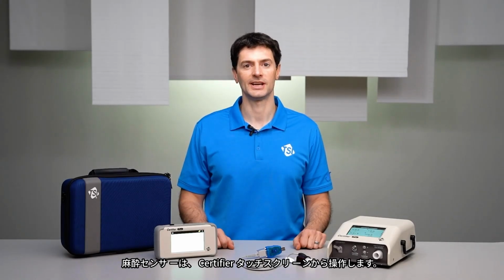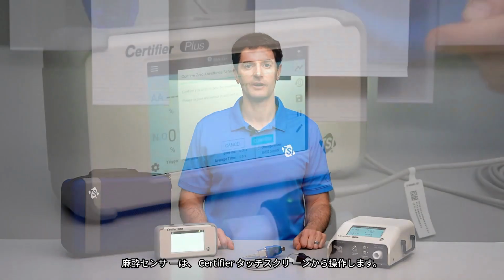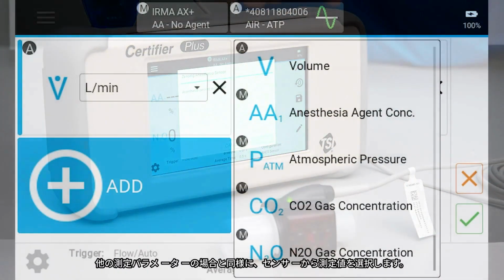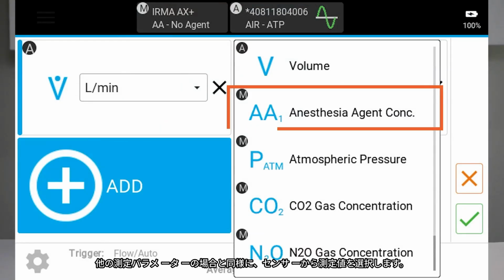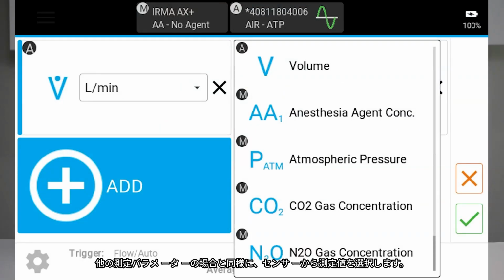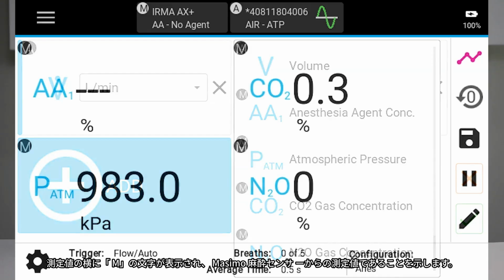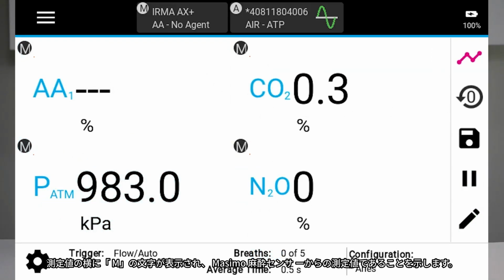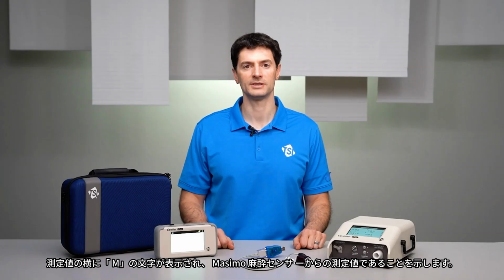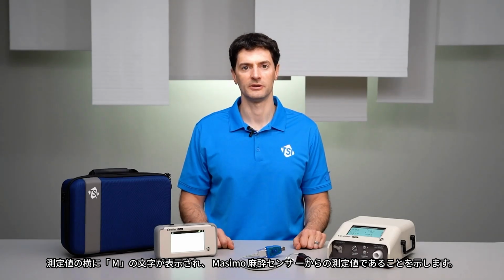The anesthesia sensor is operated from the Certifier touchscreen. Select measurements from the sensor the same way you would for any other measurement parameter. The letter M will be displayed next to measurements to indicate that they come from the Masimo anesthesia sensor.